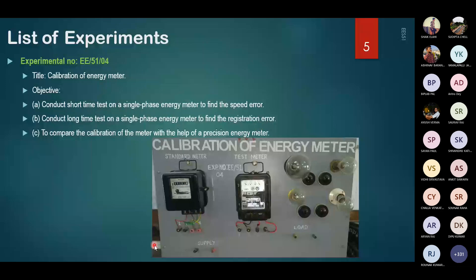So this is the energy meter laboratory setup. Here you can see standard meter and test meter, and it is the load connected over here. So we will measure the energy consumed by this load. The load here means lamps are connected, and we will also verify what is the reading in the standard meter. Comparing these two, we will find out the percentage error.